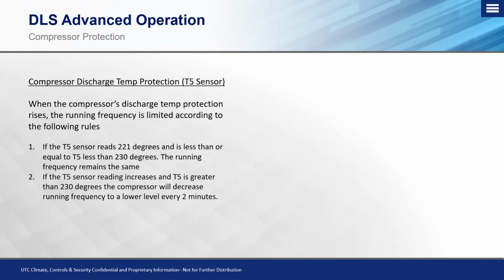Okay. If that T5 sensor is reading greater than 230 degrees, the compressor will decrease that running frequency to a lower level every 2 minutes. And like I stated before, it realizes that 230 degrees, okay, I need to throw countermeasures to bring the temperature of that compressor discharge line down. Am I going to limit the running frequency of the compressor? Do I need to adjust valve positioning, outdoor fan motor speed? And essentially these countermeasures are happening every 2 minutes, and it's going to sample that T5 sensor again after it's made a decision to see if it actually was able to bring down the temperature on that T5 sensor.